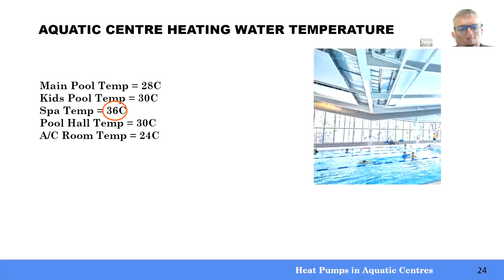So this is a typical example of what you might find in an aquatic centre, where you have the main pool at 28, kids pool at 30, and various pools at various temperatures. Always the spa is usually the hottest water that you need to heat. So if you're designing heating water to heat that series of temperatures, you'd have to make the heating water obviously hotter than the hottest water you need. And it only really needs to be 2 to 3 degrees higher than, say, the spa temperature in this case. So 39-degree heating water would be adequate.